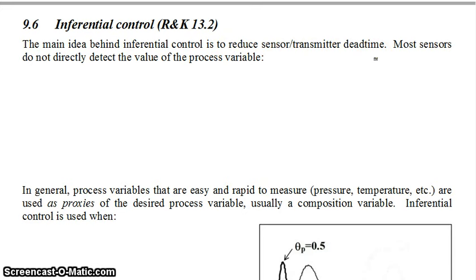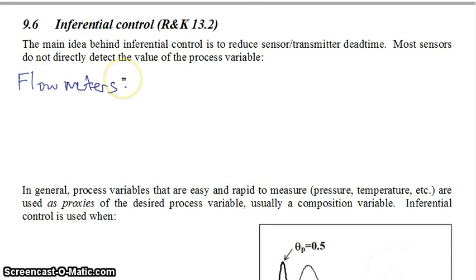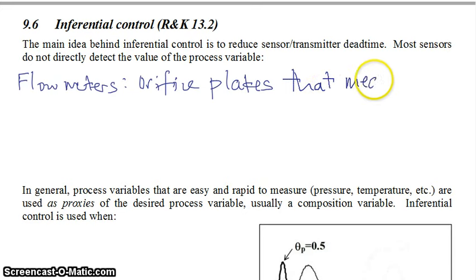Inferential control really happens all the time, and the reason why is because most sensors don't actually directly detect the value of your process variable. For example, flow meters are often orifice plates, and they don't actually measure the flow — orifice plates measure a change in pressure.